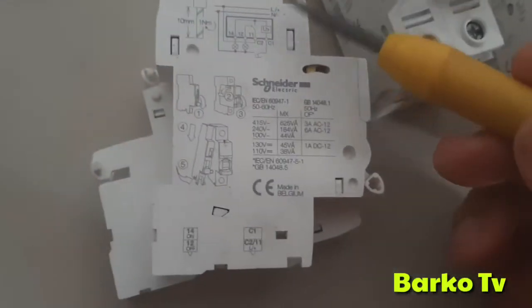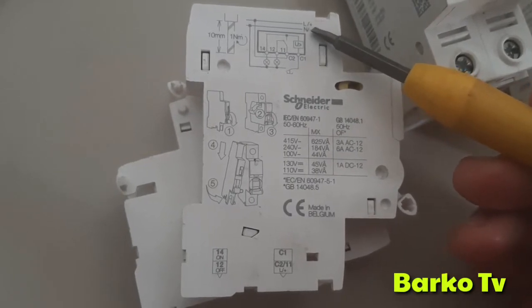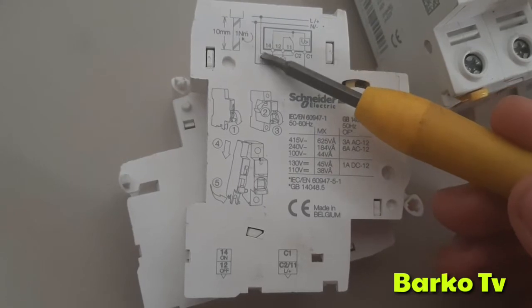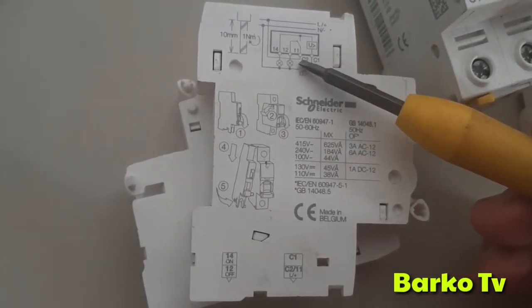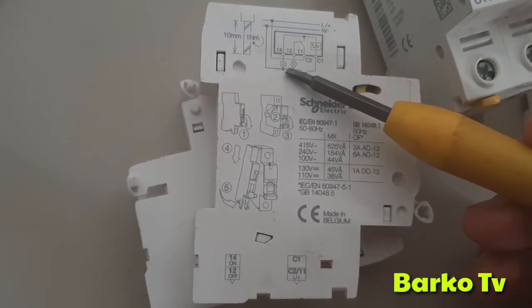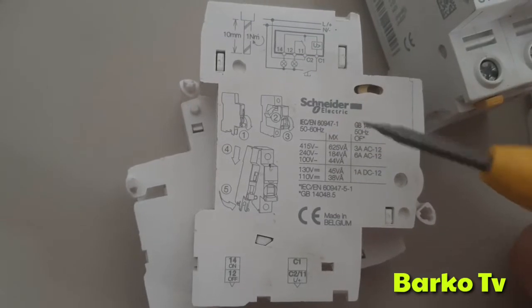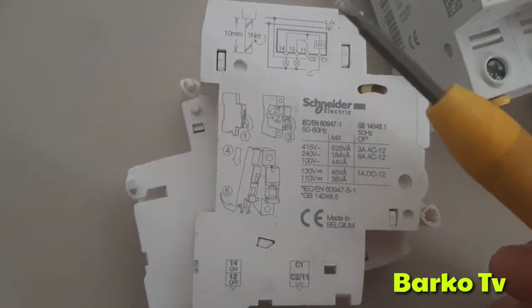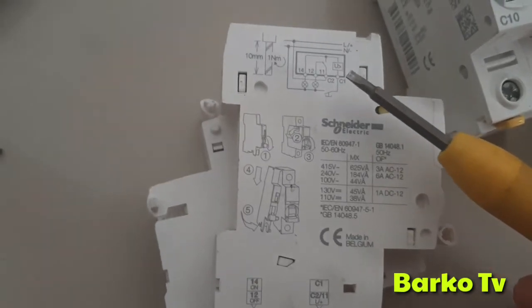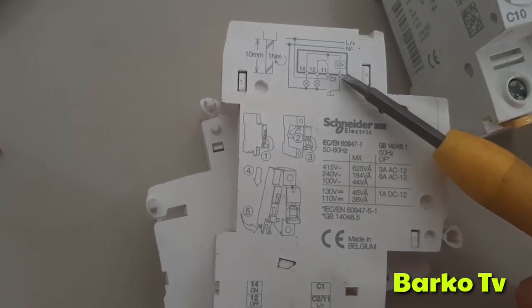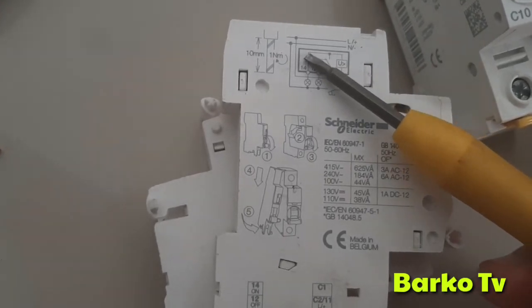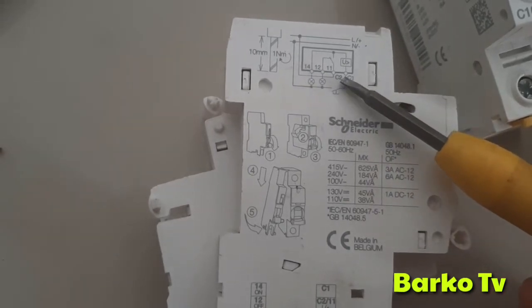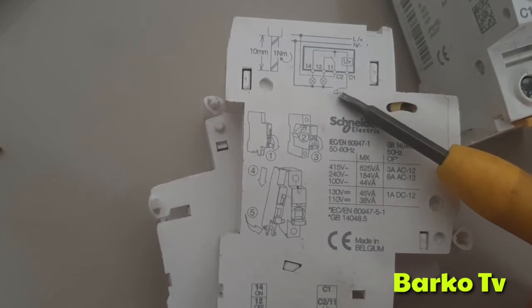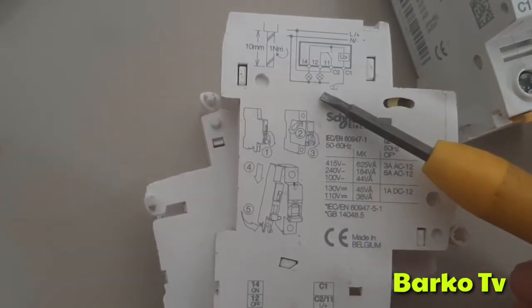At this point, I show you the terminals and its contacts. This one is the supply, positive DC or AC. It goes, this one going to C2, out to terminal 12 goes to the neutral, means for the DC, but for the AC it's line 2. But you can put indicator lights on terminal 14 and 12. This one, C1, is the coil. You can also put a monitoring on it, indicator monitoring. This is the push button going to the line 2.